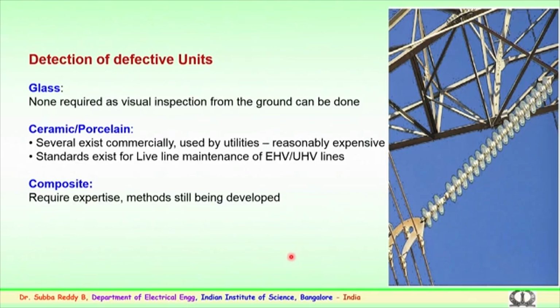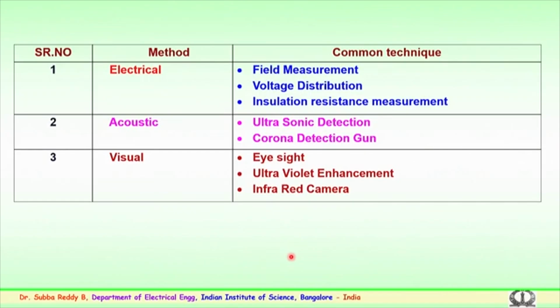There are methods yet to be developed for the maintenance, live line washing and cleaning of composite insulators, and also methods for detecting faulty insulator strings. Presently these are some of the methods. Electrical methods, the techniques employed, are field measurements. It could be using sensors. The voltage distribution method is normally conducted in laboratories, where the voltage is measured across each disc in a string and the percentage voltage distribution is found out, and it could be seen that an insulator string which has a fault could be rectified, and that this particular disc has to be changed.